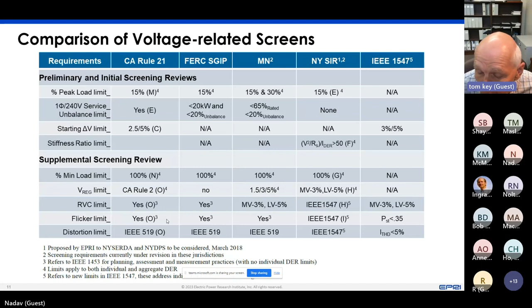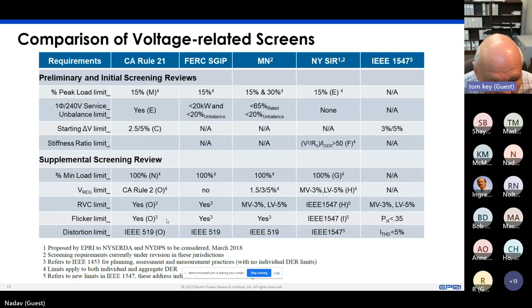Okay, I see another note. I think it's answering the same question. It had to do with reverse power in something like a low voltage network, could be a spot network or in a city network. That's a particular issue because the network protectors are often opening immediately if they have backfeed, which could cascade into an outage for the customer. So we're working on that actually on several projects to look for ways to modify the network protectors to allow backfeed. So everything is leaning toward more backfeed because it's a trend, right?